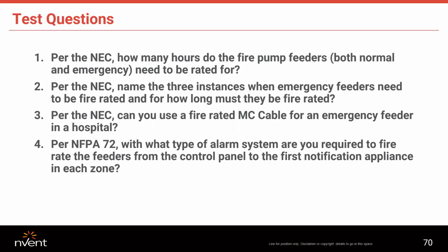Another question: if you have a fire protection sprinkler system in the building, wouldn't it be easier to have sprinkler heads above the ceiling to protect the feeder? Again, for emergency feeders, that is permissible if the sprinkler system is directly protecting the feeder. However, putting the sprinkler heads above the ceiling can be very costly. Most systems are designed where the sprinkler head comes from the suspended ceiling directly into the room, and putting the heads above is a great expense. Ensuring those heads are protecting that circuit for the entire run is also quite costly. So at the end of the day, using a fire-rated cable is going to be much less expensive than installing a sprinkler system dedicated to directly protecting the emergency feeder.